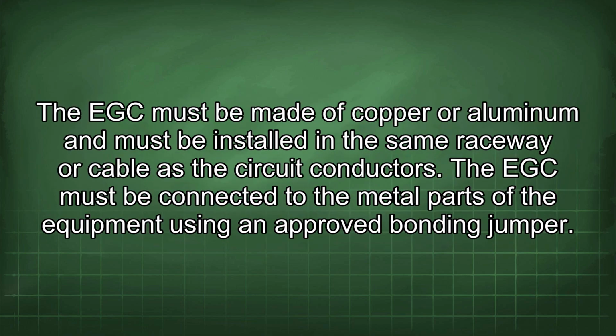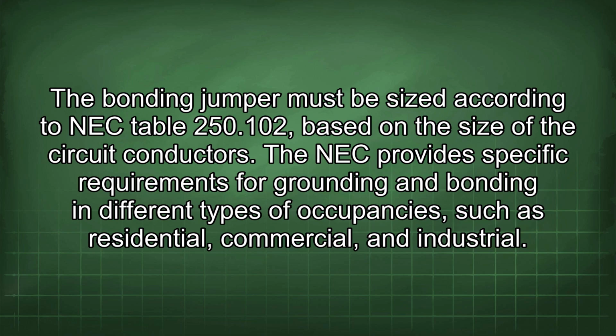The EGC must be made of copper or aluminum and must be installed in the same raceway or cable as the circuit conductors. The EGC must be connected to the metal parts of the equipment using an approved bonding jumper. The bonding jumper must be sized according to NEC Table 250.102, based on the size of the circuit conductors.